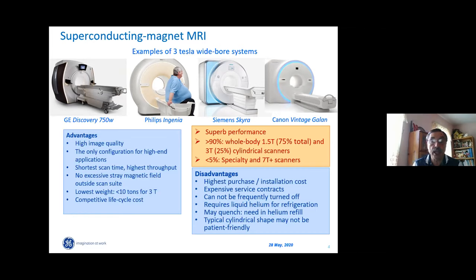It's the shortest scan time and the highest throughput of patients. We can limit the magnetic field outside of the scan room. It's the lowest weight system and has competitive life cycle cost. Obviously, there are disadvantages. It's the highest purchase cost and a pretty high installation cost. Expensive service contracts. Most MRI operate in persistent mode. We never turn the field off. And of course, liquid helium. Quench also happens, although the great majority of MRI never see a quench in hospitals.